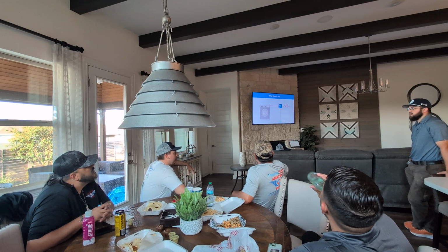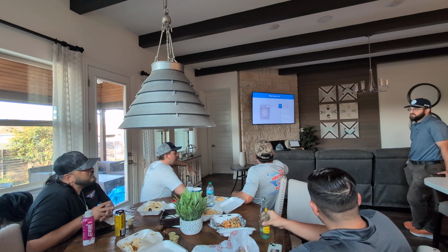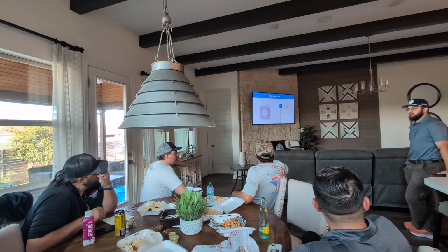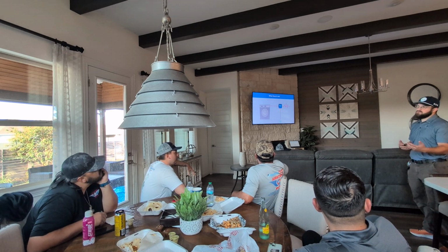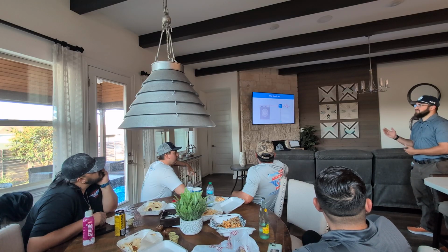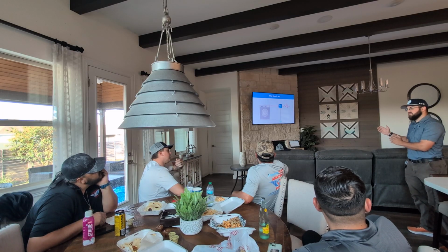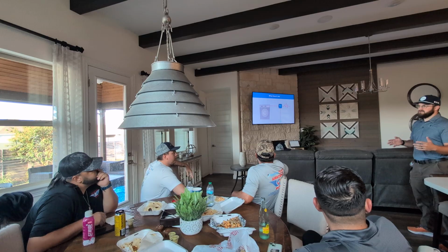If they don't have an adequate grounding system, the surge protection is only working at half capacity. So what we want to look for, especially on really older homes, anything after about 2000 you're not really going to have to worry about it, but anything before 2000 for the year built, we want to check to make sure they have ground rods.